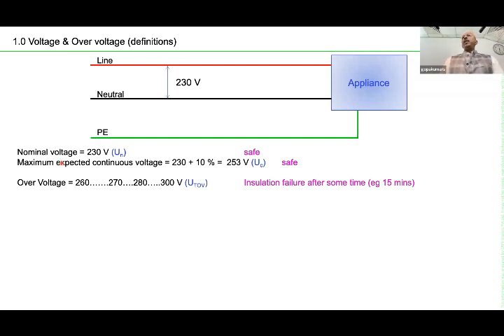Then any voltage more than the maximum continuous operating voltage, let's say 255, 260, 270, such voltages can also come into the line, and they can exist for a longer time. So here, if the voltage is more than, let's say, 260, 270 volt, some of the equipment may fail. It depends on the kind of equipment which you are using.